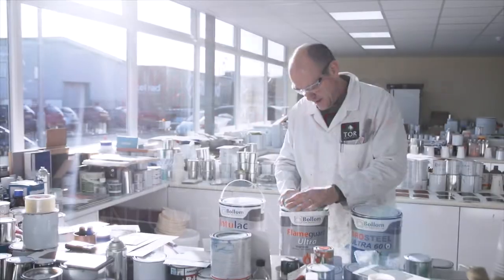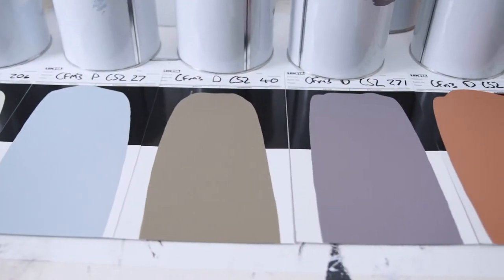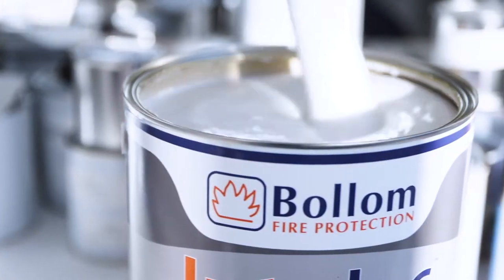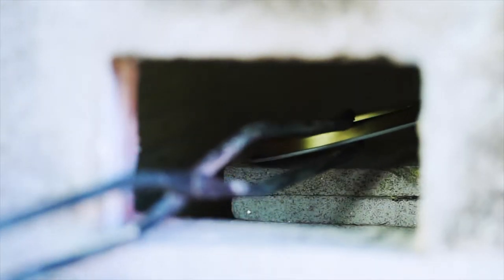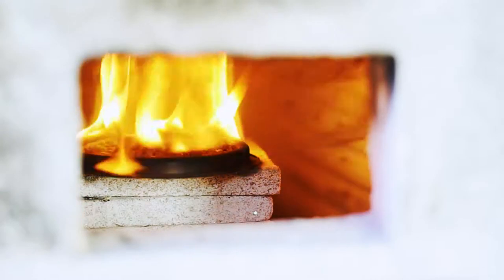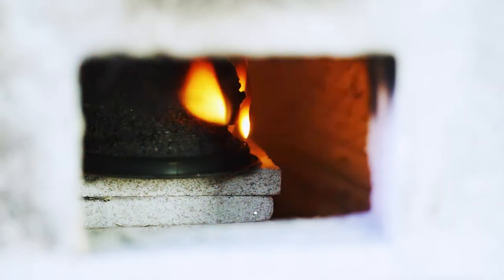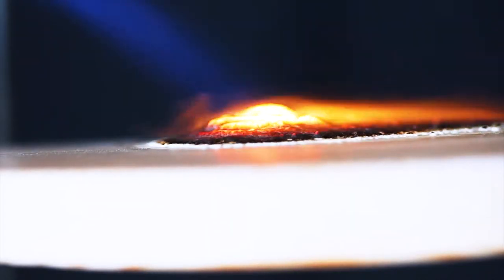Since the early 1970s, we at Bollom have developed our passive fire protection technology to create a range of decorative intumescent coatings for structural steelwork, timber, and broad wall and trim areas. When exposed to heat, our paint swells, increasing in volume and decreasing in density. The result is the creation of a light char which is a poor conductor of heat, acting as an insulating coating that protects underlying materials from heat and reduces the rate of surface spread of flame.